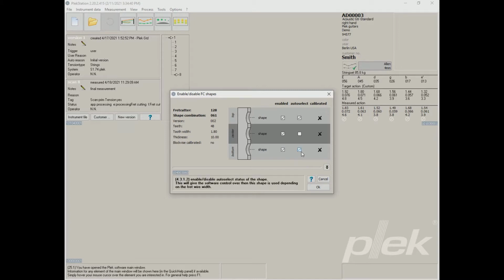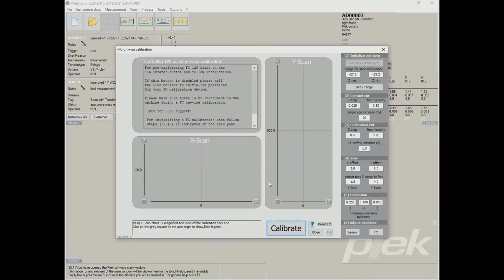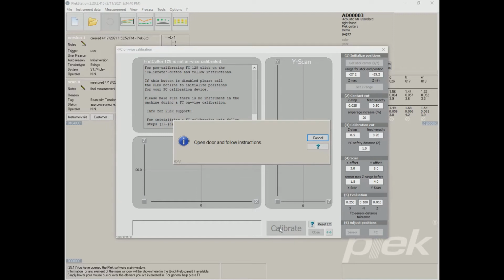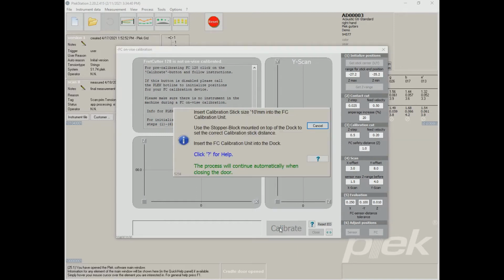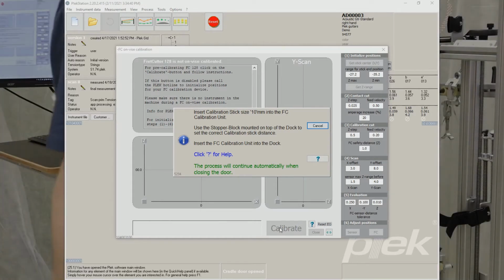That all depends on the size of the fret wire that you've entered. The machine will either select the top or the bottom shape. The center shape here is not auto selectable. You can, if you are in the virtual fret dress graph, activate the center shape. These crosses mean that these shapes are not calibrated yet. So what do we do? We click on OK, and now we come straight into the calibration window. When we click on calibrate, the machine wants me to open the door, and we take our FC calibration unit.